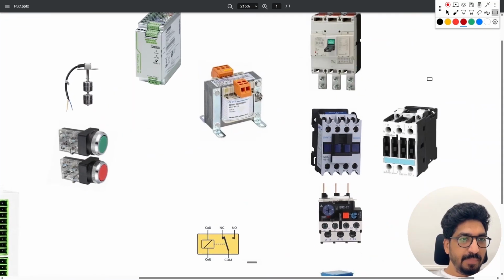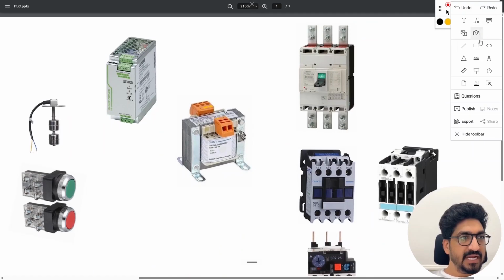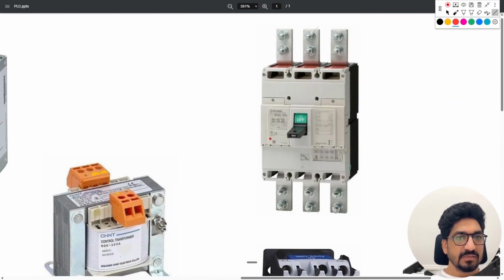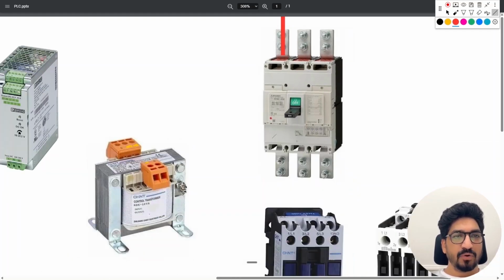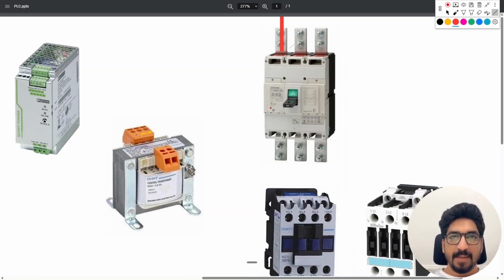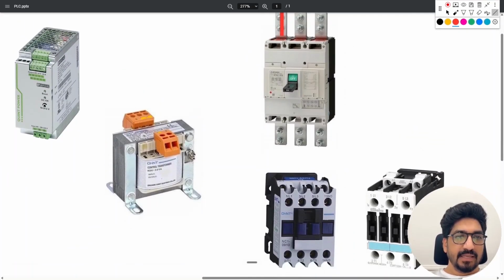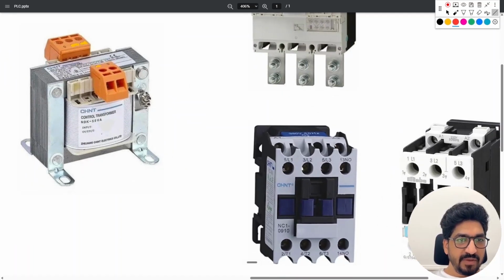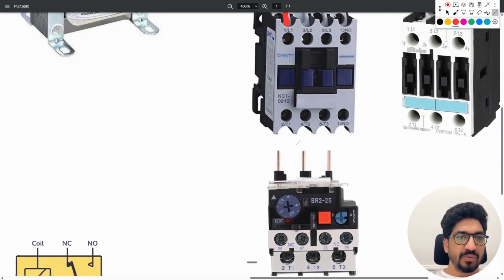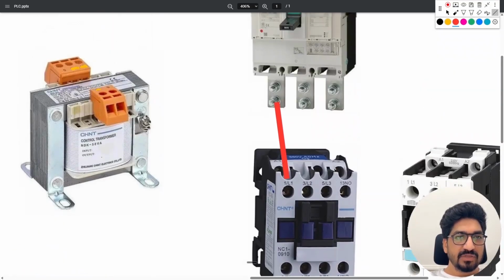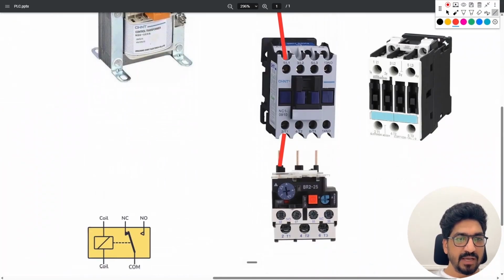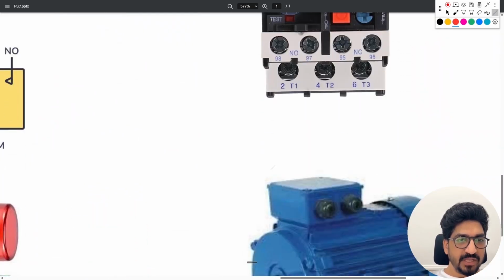All right, let's power this up. Firstly we need power input, three phase. Let's suppose the power input is coming from the top, from somewhere - perhaps the main switchboard. Then it goes, we connect this to the contactor. These wirings will be done normally. I'm connecting the red phase wire first, and from the OCR, output is coming from T1 and it goes into the motor like this.